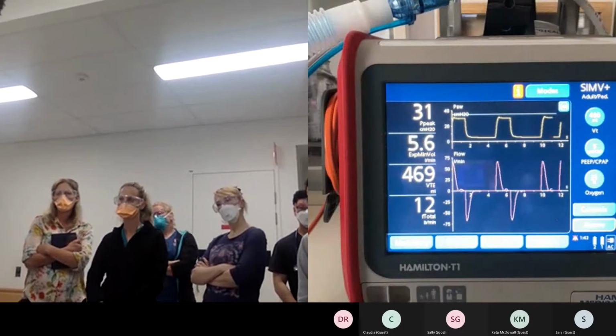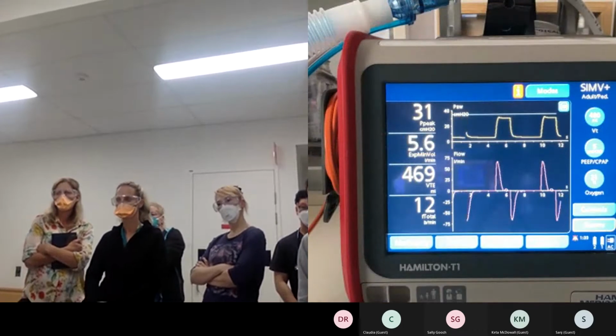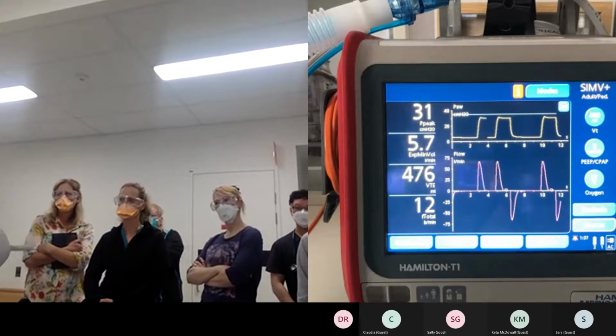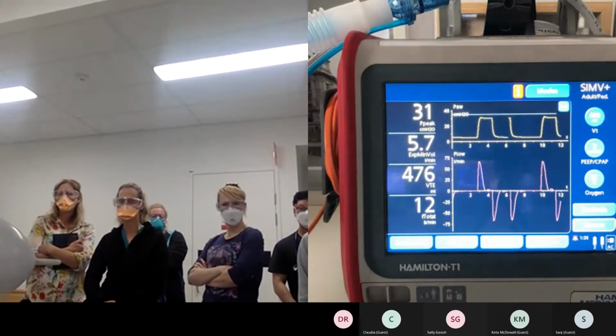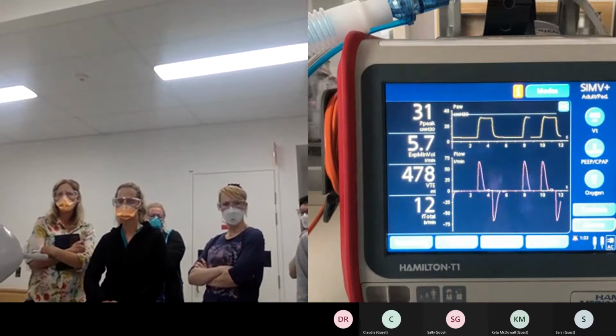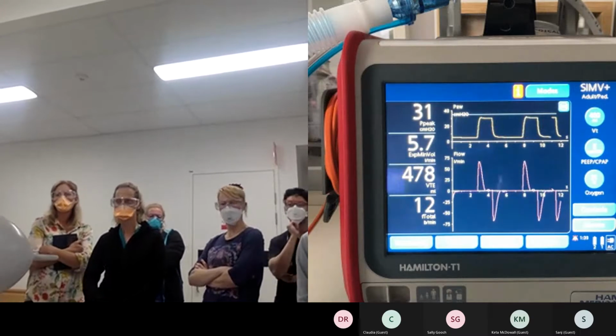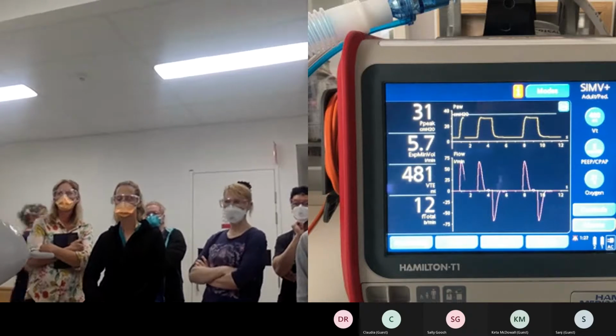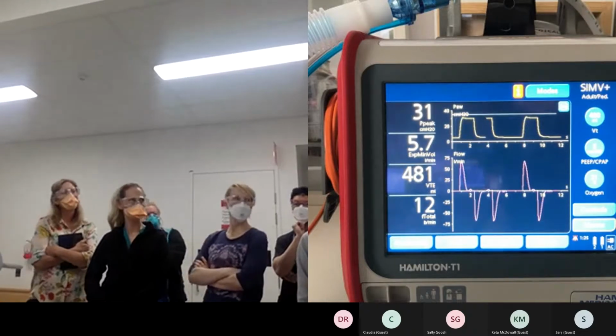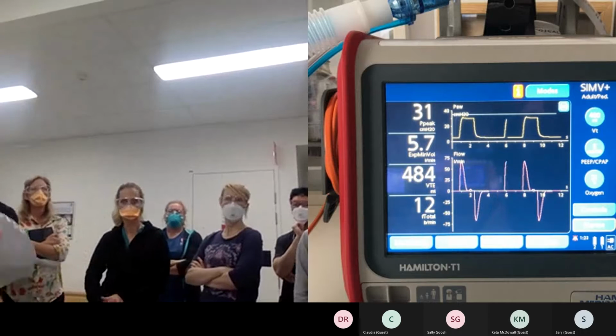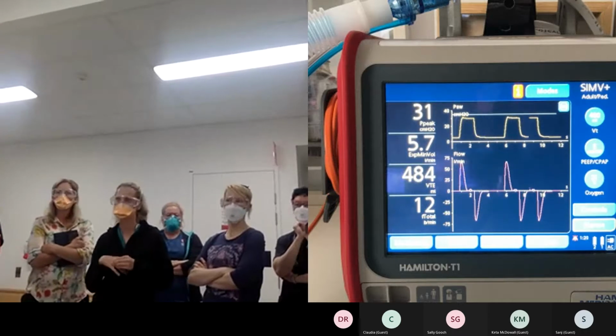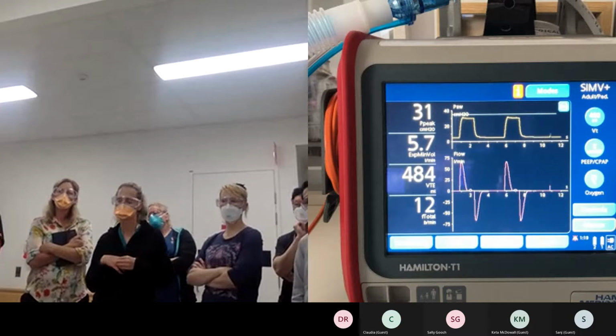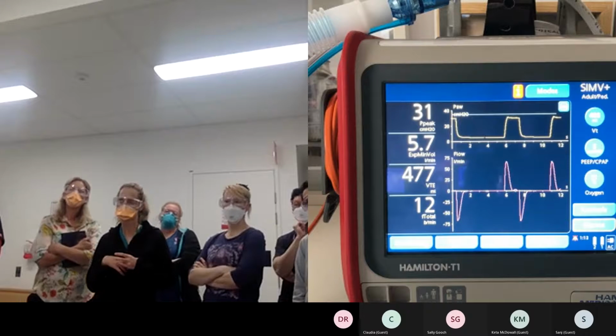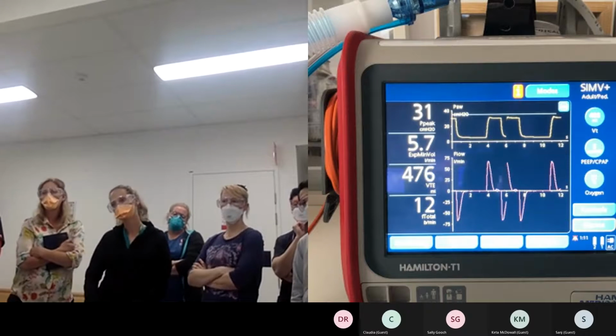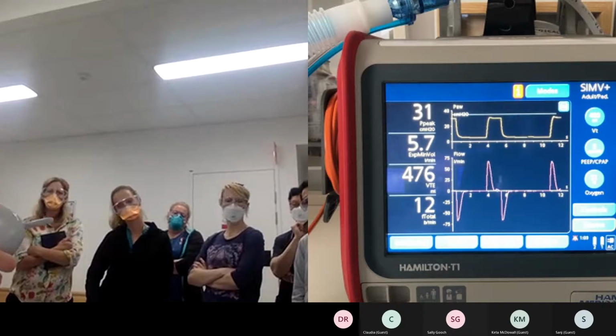Okay. So it's slightly different to if you're used to the Draeger, I think you set a P max or P limit. This one you're setting the red and the blue is 10 below it. But you can set the red and the blue line separately, or the blue is a standard? No, the blue is a standard 10 below. And it's going to cut out, so just be aware, as she said, it's going to be cutting out at 35, even when that's set to 45. Okay.